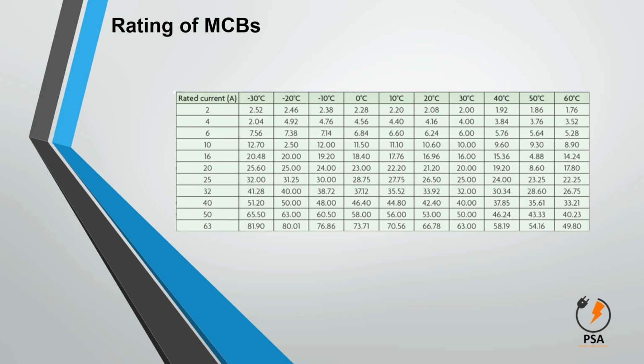The following figure shows the rated current of standard miniature circuit breakers at 30 degrees Celsius and with rising and falling ambient temperature. As you can see, the rated current of a circuit breaker decreases with increasing ambient temperature and increases with decreasing ambient temperature.